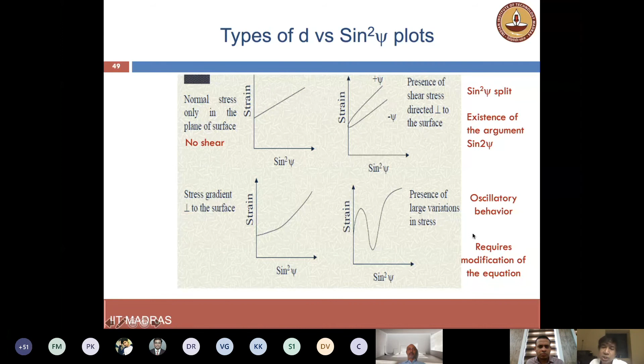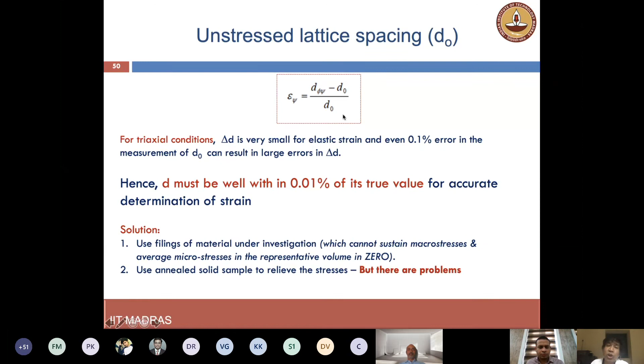It's very important that you choose d naught very accurately, because if you don't choose d naught accurately, you may end up with inaccurate results. Typically, this is taken care of in the software. You know what the d naught should be for a given material. But if it is not there, then you can get d naught by taking filings of that material and calculating it. Because filings will not be able to sustain stresses, they will be stress-free. So basically, you need to calculate d naught for samples which are stress-free.